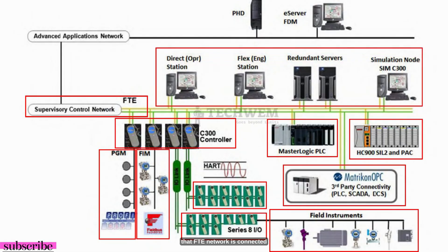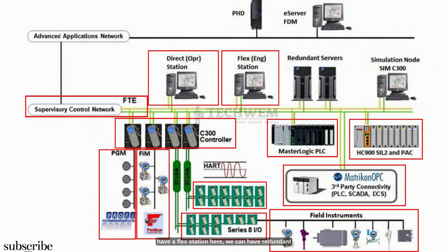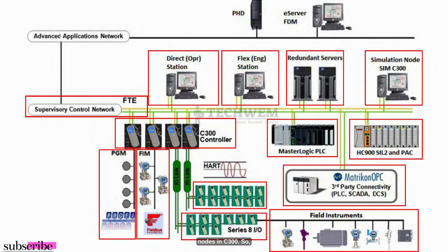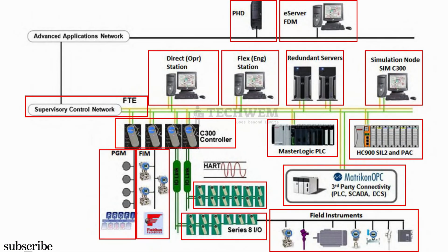That FTE network is connected to the next layer. On this layer, we can have our console station, a flex station, a redundant server, and also simulation nodes in C300. This is where you simulate your actual field process in a simulation environment — you practice and verify your process. It is especially made for control engineers and process engineers. They simulate everything here and then implement it via servers and the engineering station. On the Advanced Application Network, you connect your field device managers, which monitor field devices and their calibrations, and there is a Process Historian database which historizes your important data for future analysis.